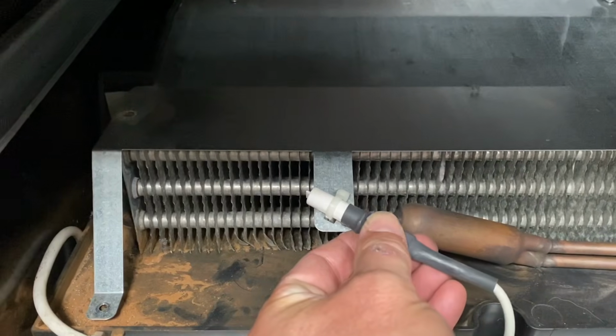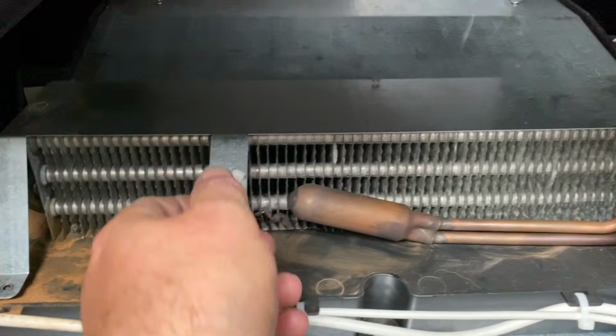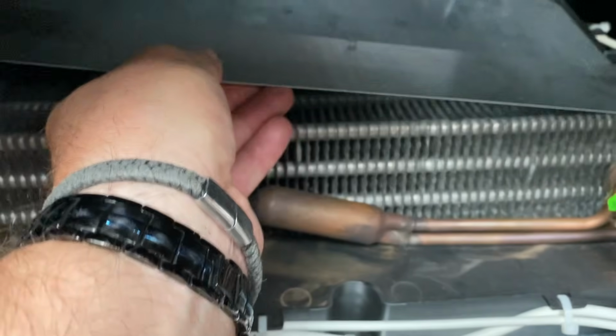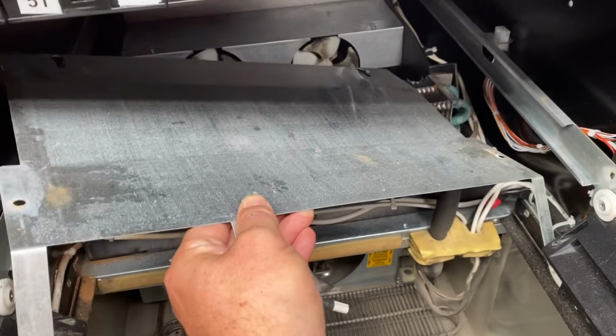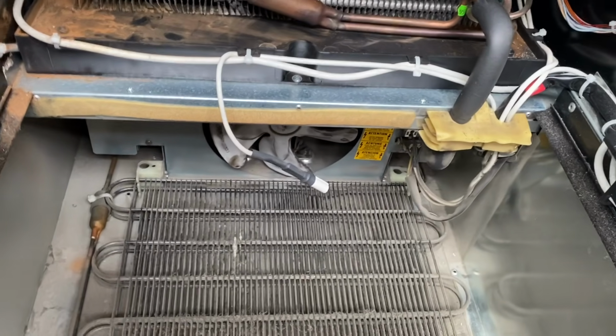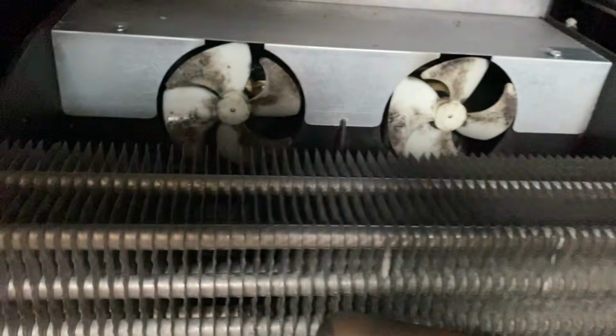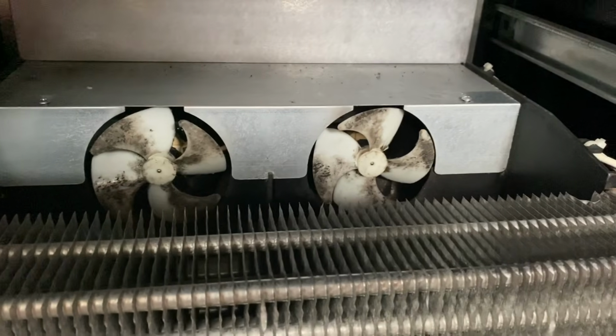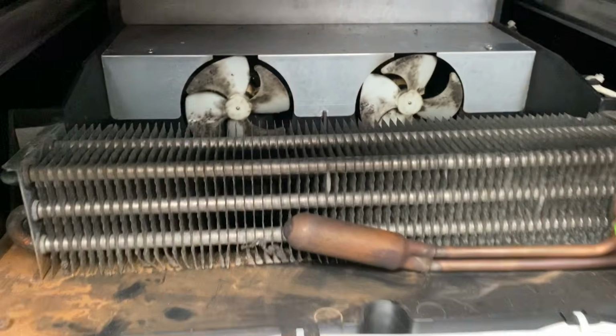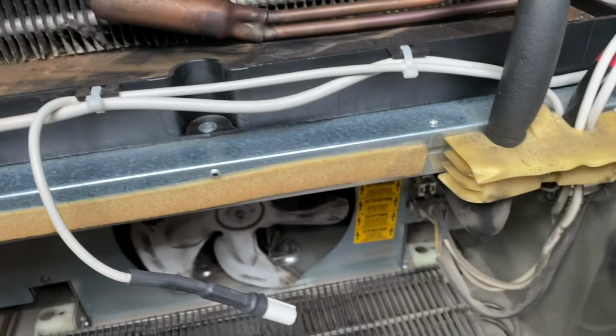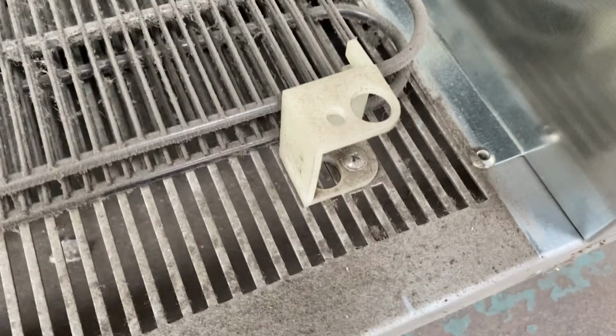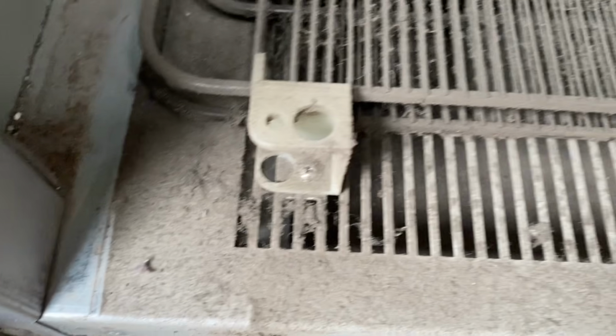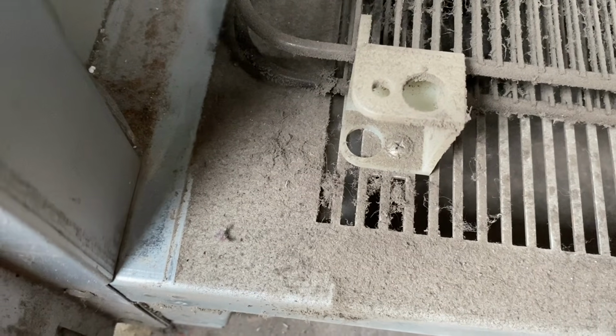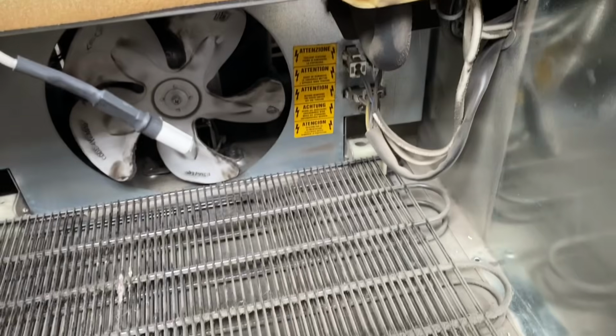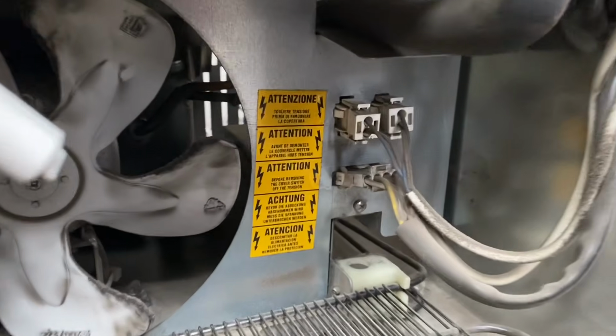take the panel off. But before you do that, just make sure that the temperature probe is removed from the silver plate, pull it forward and lift it off. Now to remove the chiller, you need to take the 2 screws off at the front. So you've got 2 brackets here, plastic brackets. If you remove those screws, once you've removed those screws, then you need to unplug the chiller.